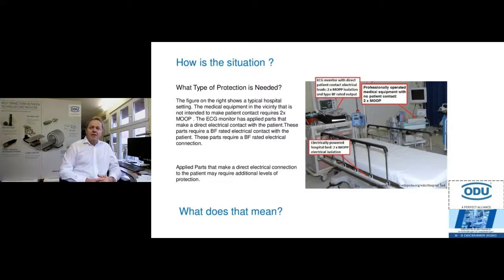The medical equipment in the vicinity that is not intended to make patient contact requires MOOP. What does it mean, MOOP? Look at my pictures and you see on the right side there is some stuff which has the name professionally operated medical equipment with no patient contact. This equipment has this MOOP. MOOP stands for means of operator protection, and it means that this equipment doesn't have any direct contact with the patient.